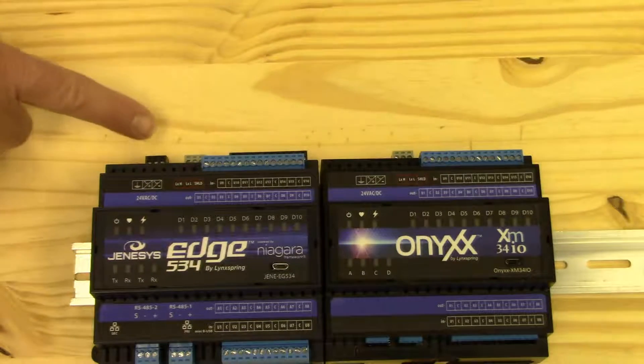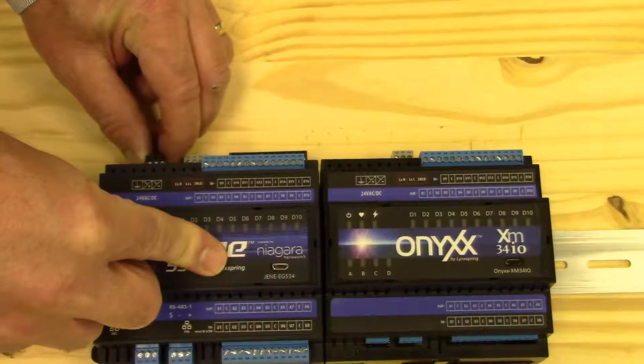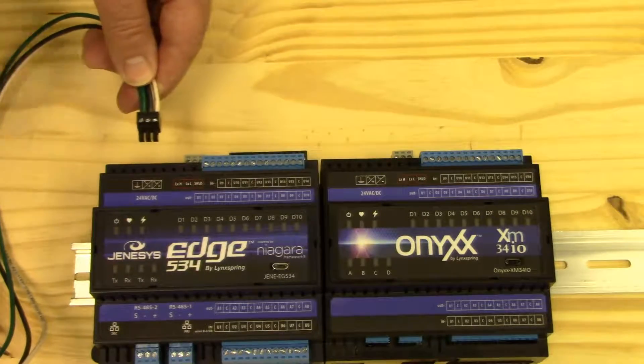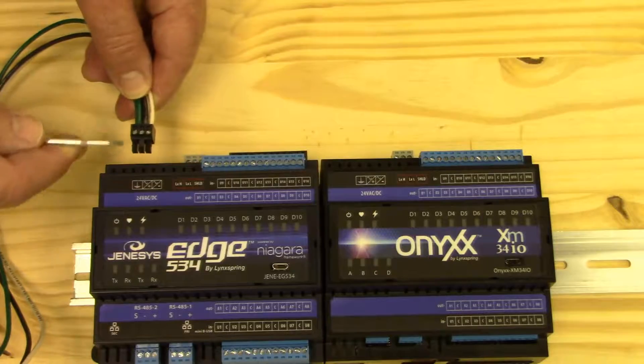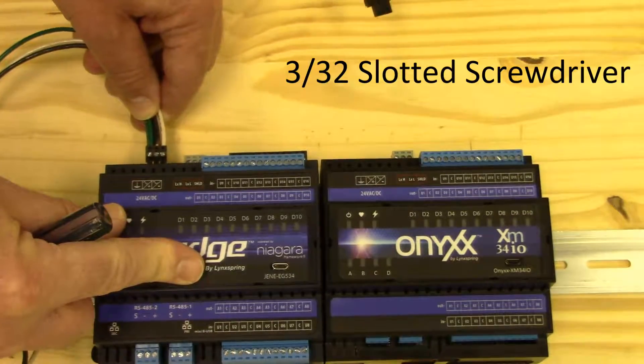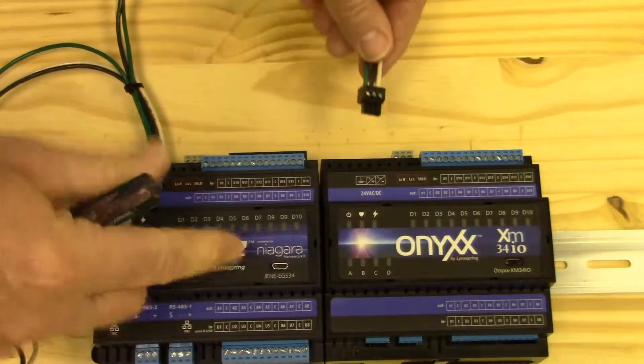To apply the power, we use this 3-terminal block. I'll pull it out, and for our purposes here, I've already pre-wired it. The wires I'm using are 16-gauge, and I used a 3/32nds slotted screwdriver. You want to tighten those down and plug it in — generally it'll click, and you'll know it's in.